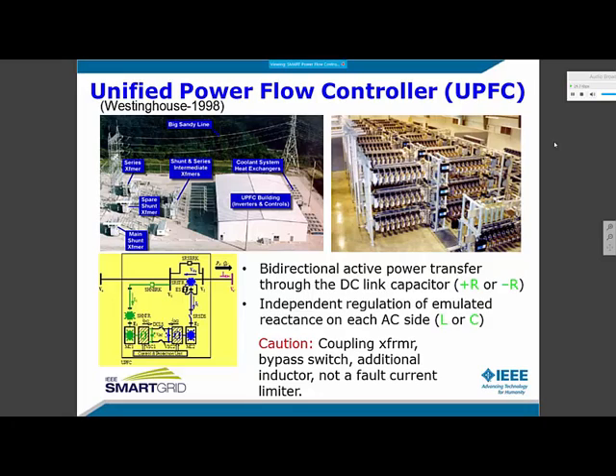The desirable bypass switch is an electronic bypass switch on the high voltage side of the line. But no one uses a bypass switch on that side of the line because it's too expensive. So a cheaper solution is to use a mechanical bypass switch. But that mandates using an electronic bypass switch on the low voltage side of the line. And this also requires an additional inductor so that the inverter does not get shorted and carry high short circuit current during the time when the electronic switch operates. So that additional inductor reduces the good capacitive rating of the inverter even further.